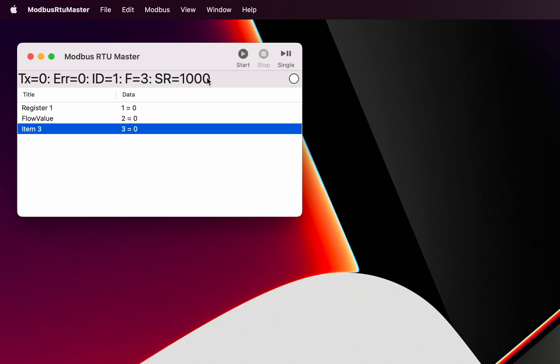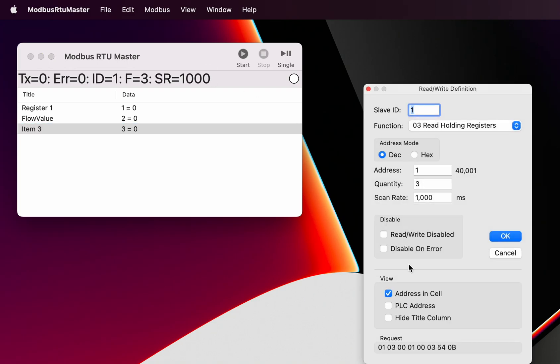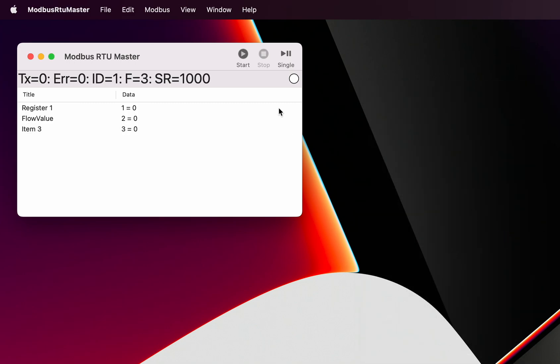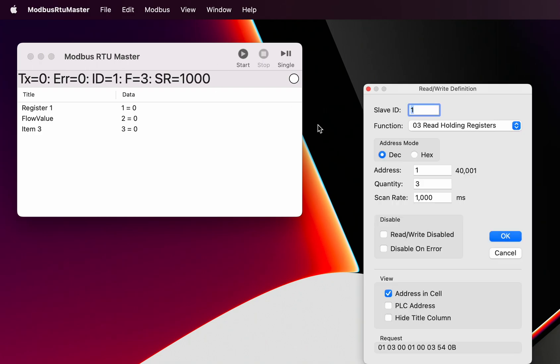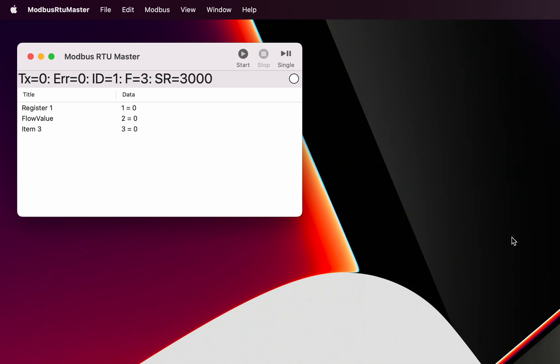Let's have another look at the scan rate that we've got in here. We've got a scan rate that we can define. When we hit the start button, Modbus RTU Master will send the request to the slave and it will keep sending that request every one thousand milliseconds in our case, or if you want to slow that down to say every three thousand milliseconds. So now every three thousand milliseconds, every three seconds, the request is being sent to the slave and we're expecting a reply to come from the slave.